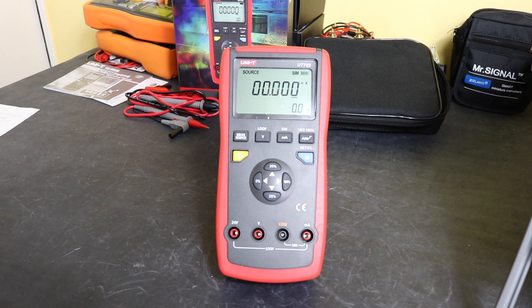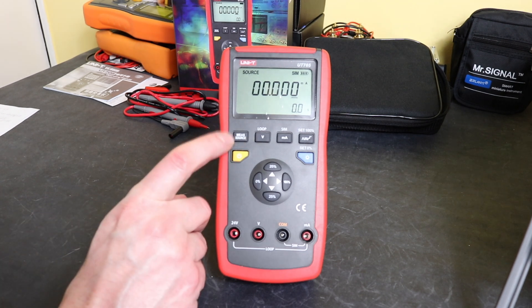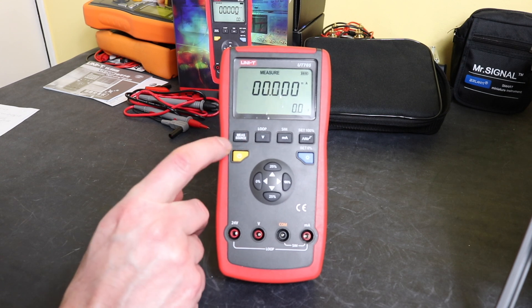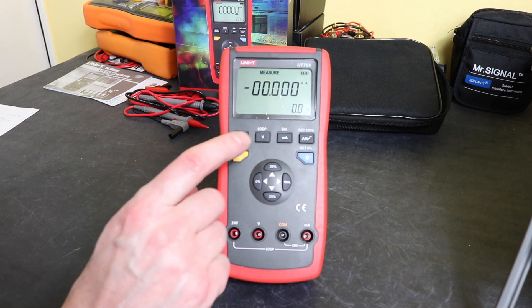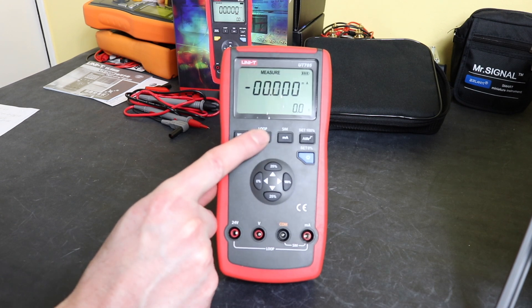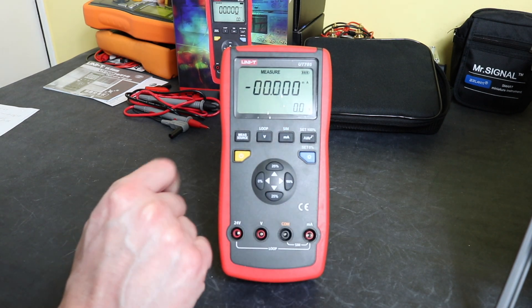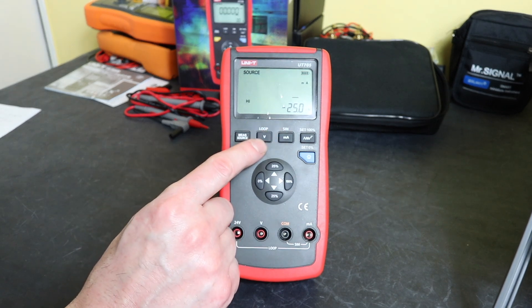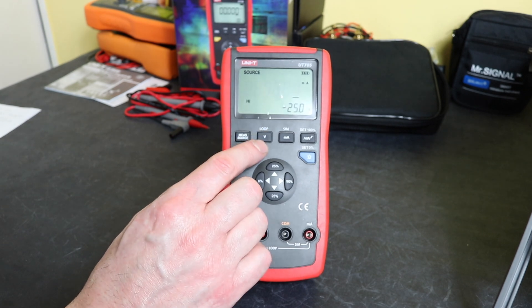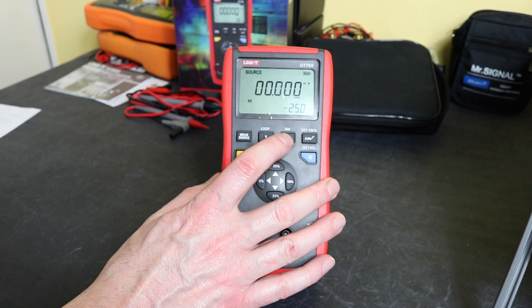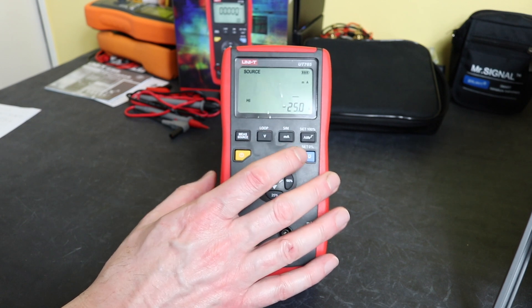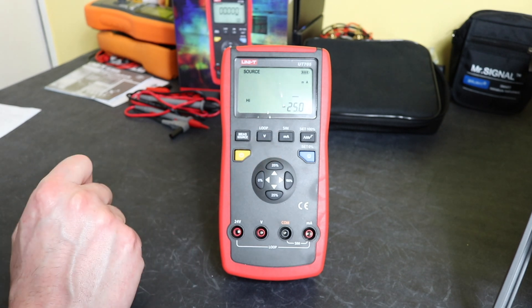In terms of the operation of the unit, you can swap between measurement and source mode on the button here at the top. You can change between voltage using the second button and then current using the third button along there. Change it back to source and then you can only source current on this. So the voltage button just changes that to the loop function, and the simulation button changes it to the simulation mode which will supply 24 volts for a loop powered transmitter.